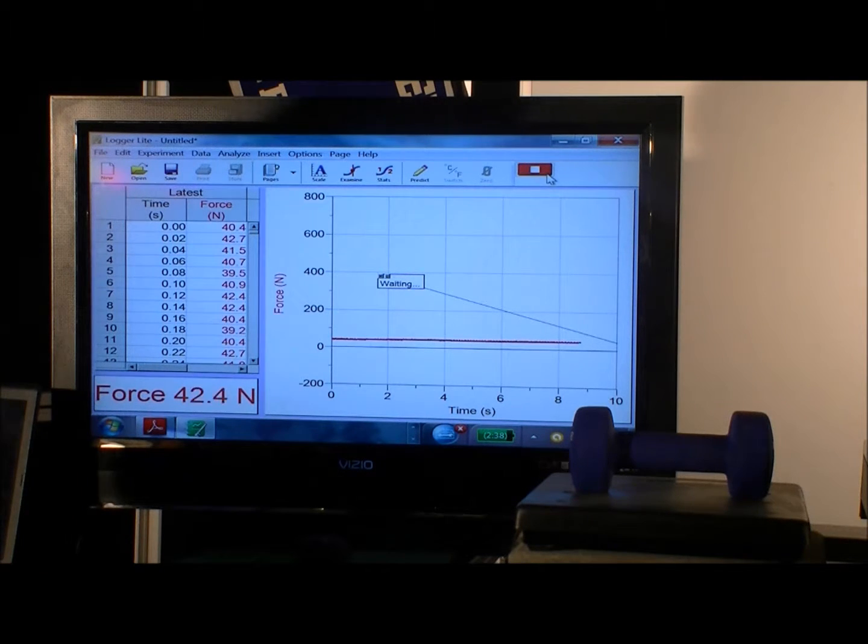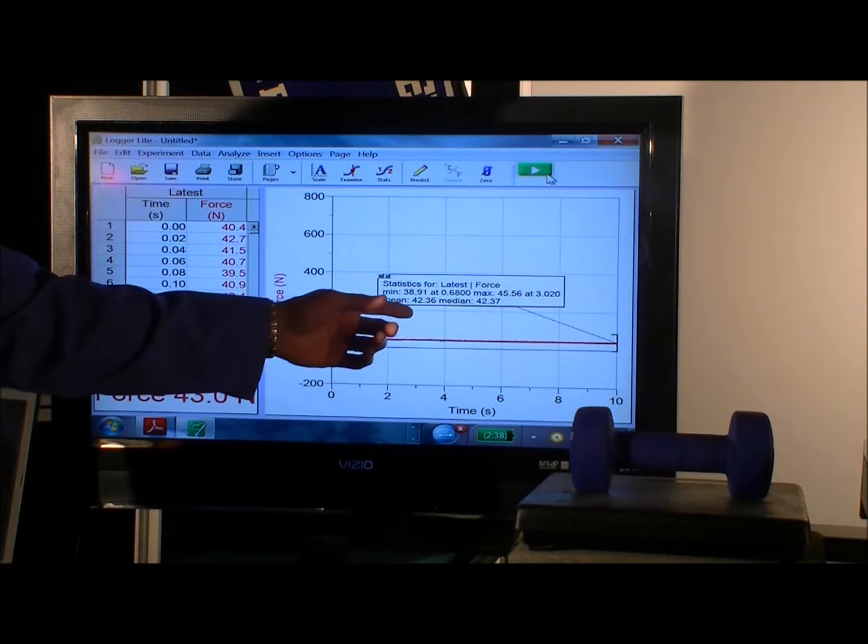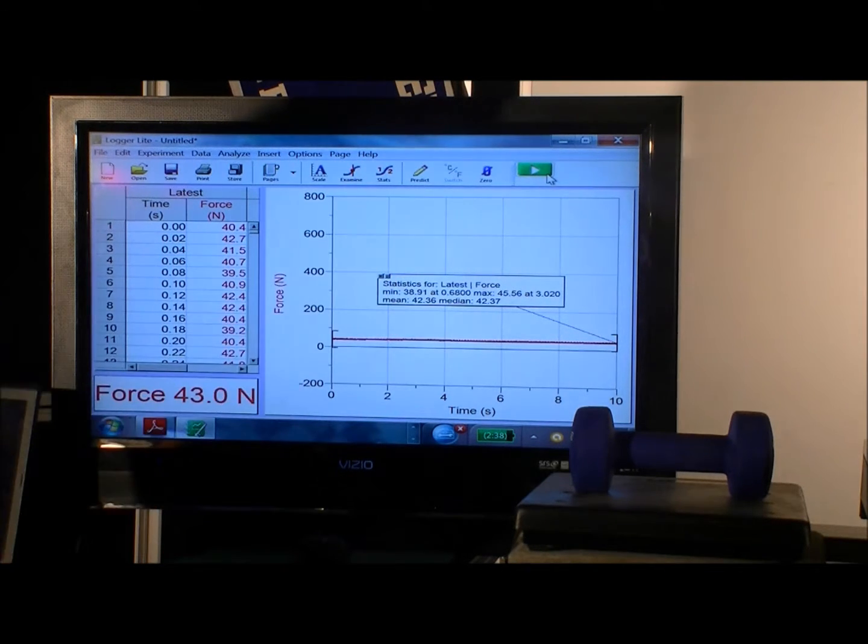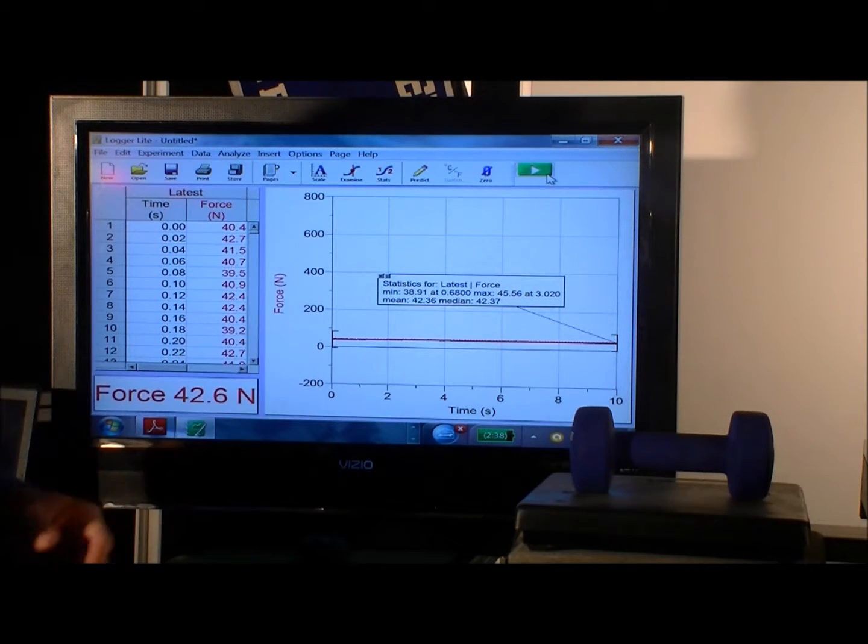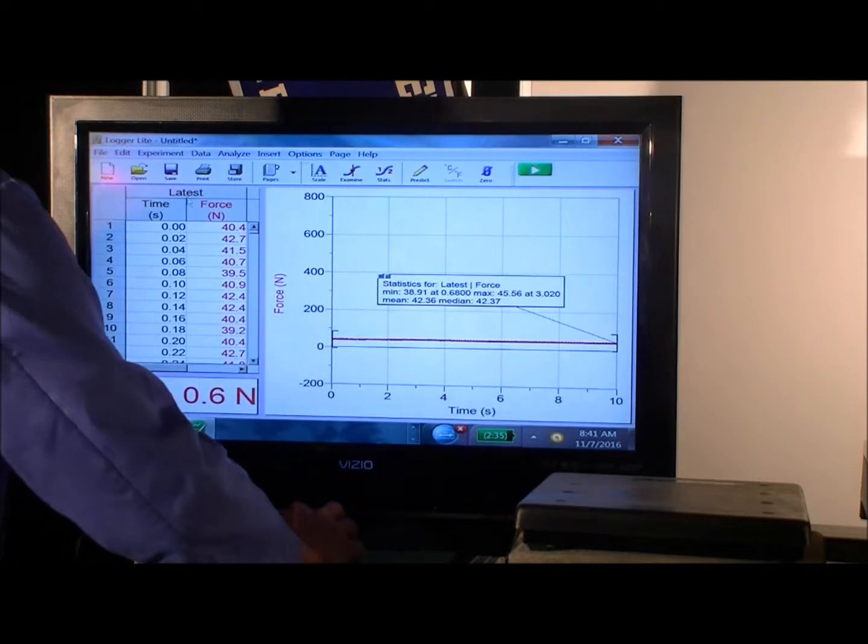And now let's go ahead and average for 10 seconds, because if you just leave the static situation on there it'll average over the 10 seconds and then we can see. So now it says that the mean is 42.36, and 42.36 is within 1% of 42.28, so now we've got some confidence in our calibration.